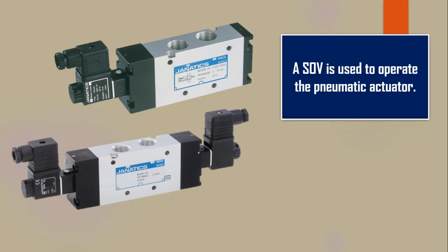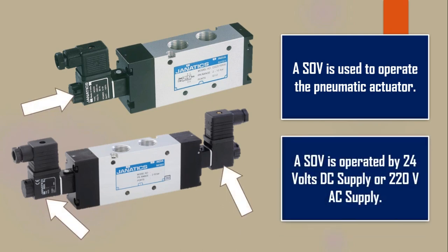A SOV — solenoid valve — is used to operate the pneumatic actuator. That means a solenoid valve is used to provide the signal to the pneumatic actuator. Here solenoid valves are shown in the picture. A SOV is operated by 24V DC supply or 220V AC supply. The supply is given to the solenoid coil, and here solenoid coils are shown by these white arrows.